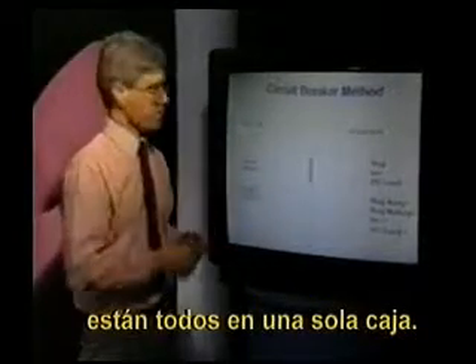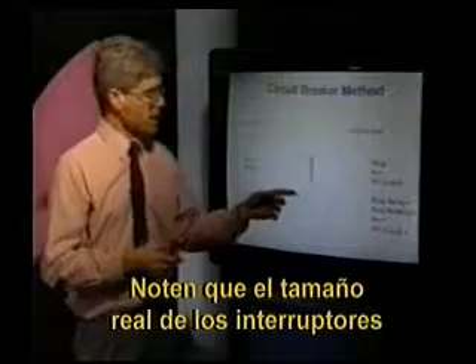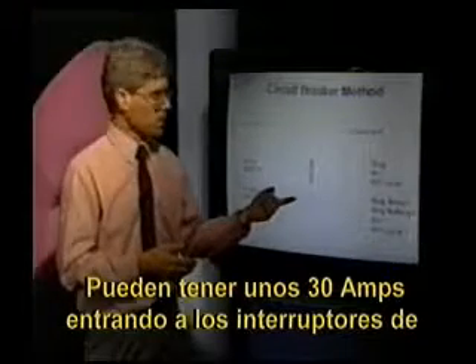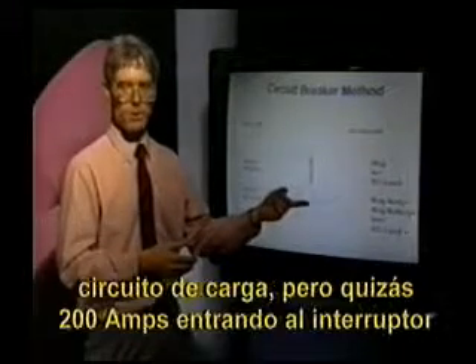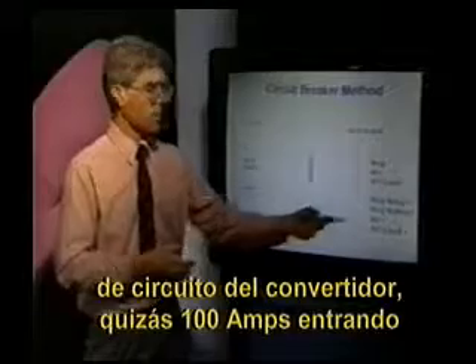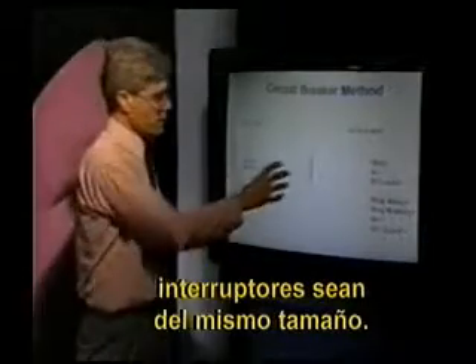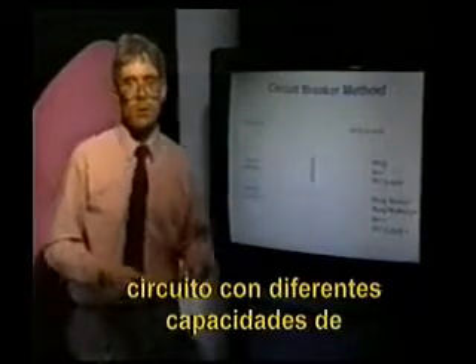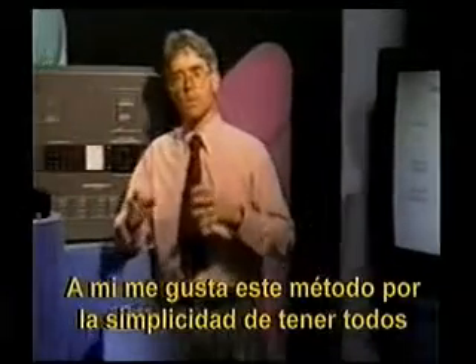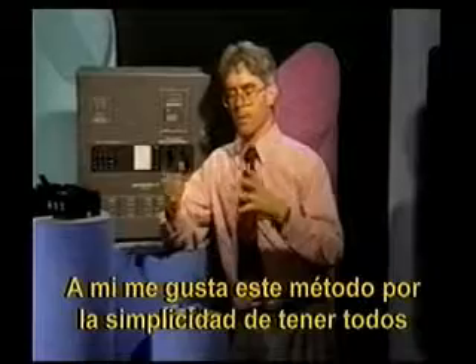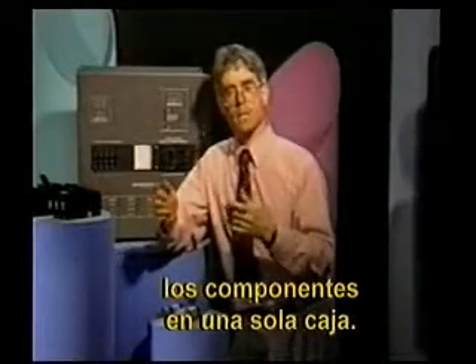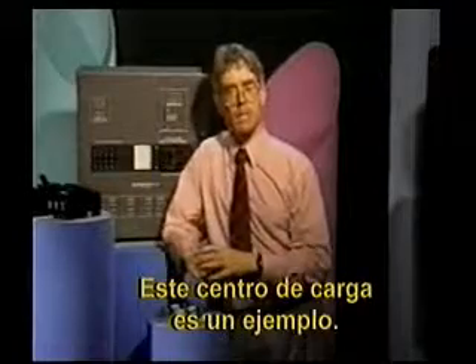The nice thing about this approach is that all of the components are physically in one box. Be careful to note that the actual sizing of the circuit breakers is going to be quite different. You might have 30 or so amps flowing in your charging circuit breakers, but maybe 200 amps flowing in your inverter circuit breaker, maybe 100 amps flowing in your DC load center breaker. The size of the breakers don't have to be equal at all. So in this approach, we could physically put together circuit breakers of different current carrying capacity. I like that approach. It involves simplicity in terms of wiring, having all of the components physically in one box. An example of that would be a load center like this.